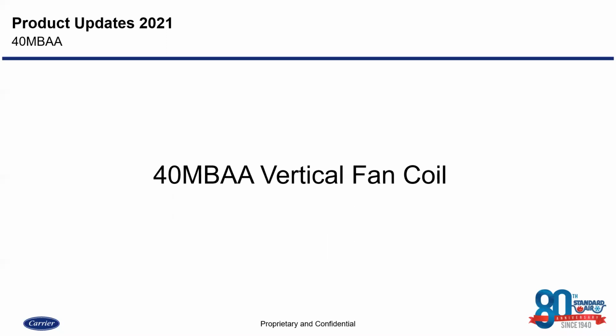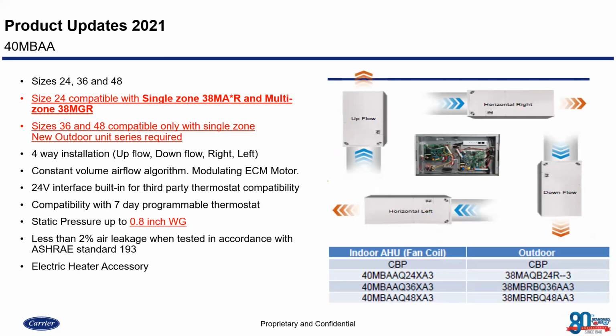So let's look at an overview of the 40 MBAA vertical fan coil for ductless systems. This vertical fan coil is a true ductless indoor unit, which means it does not require that piping adapter or that TXV removal kit that we see with the hybrid solutions. So technically this is not considered a hybrid solution, as it is a true ductless indoor unit. It does not have an expansion valve at the indoor unit. Just like any other ductless system, the expansion valve is going to be located at the outdoor unit. So all we really have to do to this unit, from a piping perspective, is hook up our piping and then of course do our corresponding wiring.